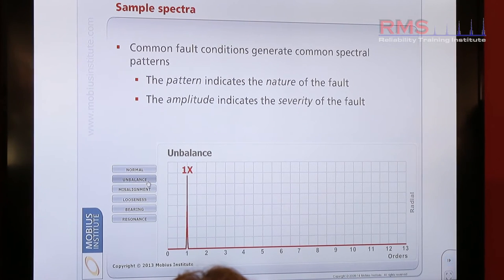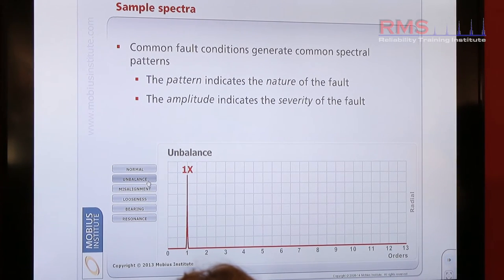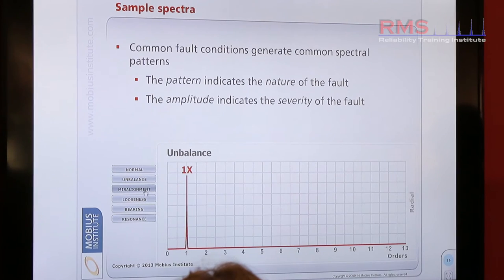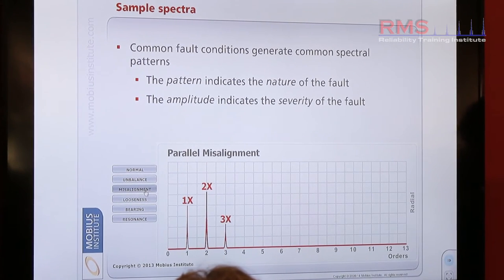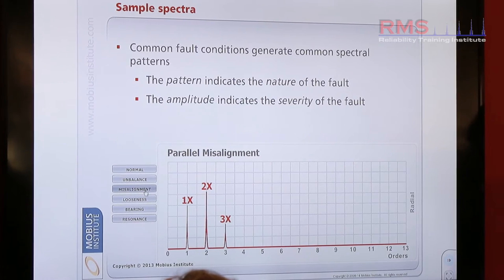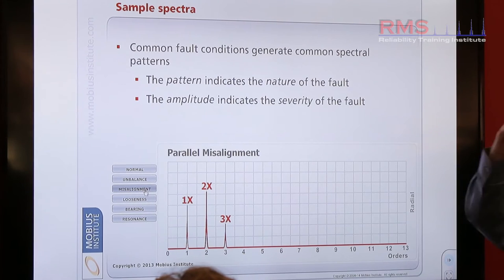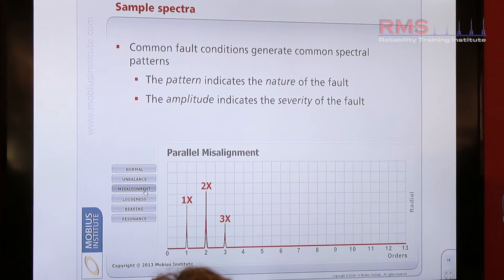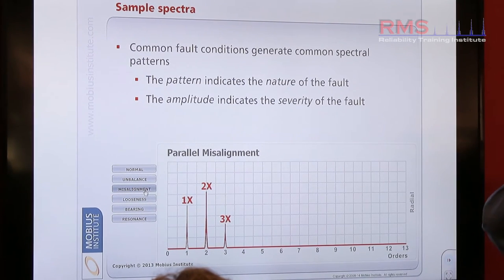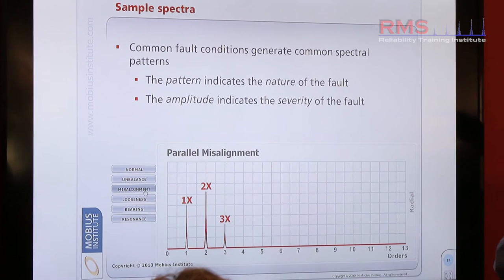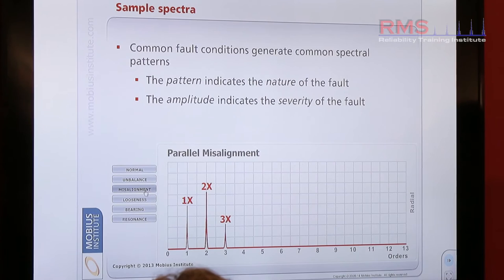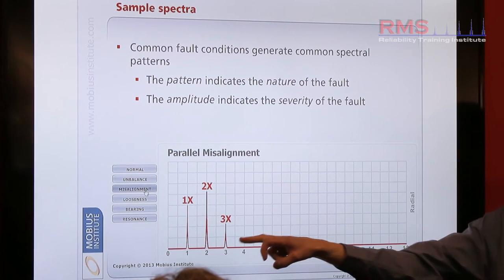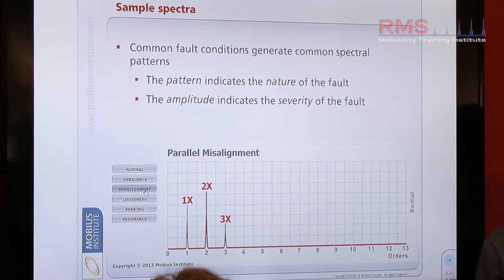Our software — we click on the peak and we're told it's once times the speed. Maybe if two shafts are not aligned — motor and pump should be perfectly aligned — but maybe one is shimmed higher than the other. Think about the forces, think about the motion as it rotates: one rotation, one pulse, two pulses. So two pulses per rotation, producing a very distinctive characteristic second peak.